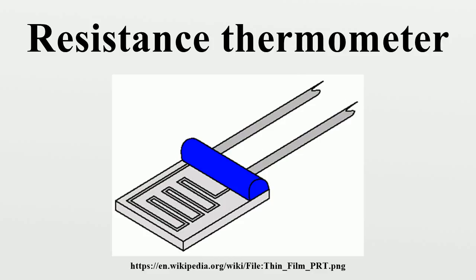than thermocouples. While thermocouples use the Seebeck effect to generate a voltage, resistance thermometers use electrical resistance and require a power source to operate. The resistance ideally varies nearly linearly with temperature per the Callendar-Van Dusen equation. The platinum detecting wire needs to be kept free of contamination to remain stable. A platinum wire or film is supported on a former in such a way that it gets minimal differential expansion or other strains from its former, yet is reasonably resistant to vibration.